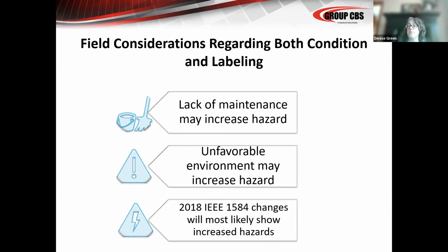I see a question in here saying, for draw out circuit breakers or switchboards, what electrode configuration should be studied? Seems like all three could be found inside these types of enclosures. Yep, all of them can be found. It just depends on the type of equipment. So if you have to do an updated label, that actual gear will be taken into account when the data collection happens. The person doing the study will be able to determine whether that gear is vertical in an enclosed cabinet, horizontal in an enclosed cabinet, all those things, and that will automatically be a part of the calculation now that it's after 2018.